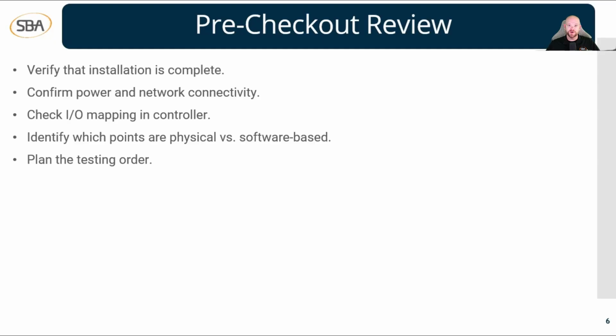The next thing is to confirm that you have power and network connectivity to the devices that need those. So, you know, for controllers and certain output devices, those are powered devices. You'll have to have power to those at all times. And then network connectivity. For your controllers, if they're BACnet IP controllers, you're going to have a Cat6 cable running between them, either in a daisy chain pattern, or if it's MSTP, you might need an RS485 twisted shielded pair wire as well. But you have to make sure all this stuff is done.